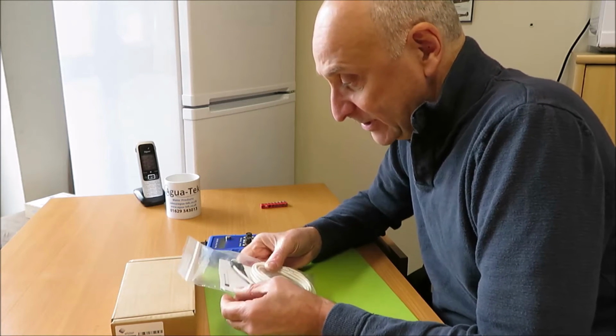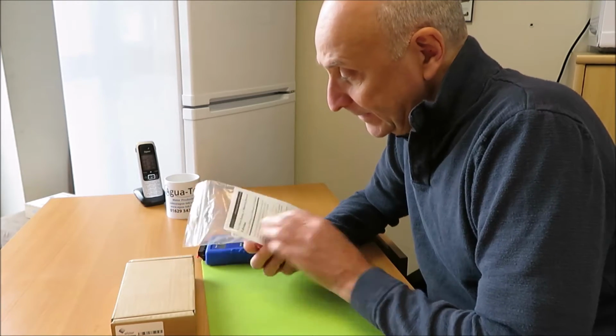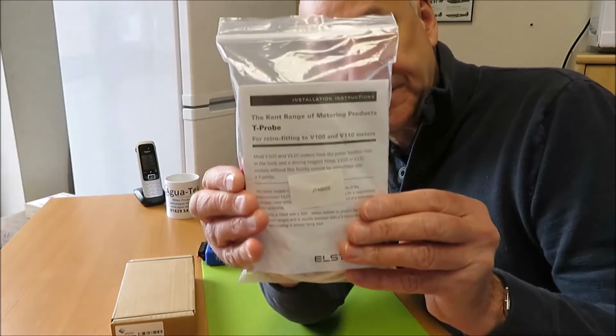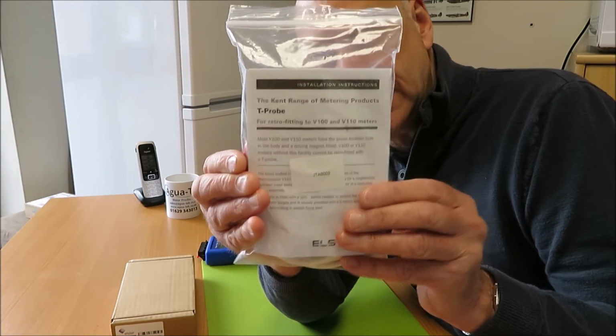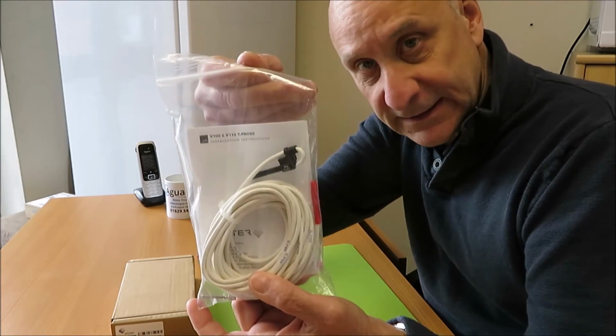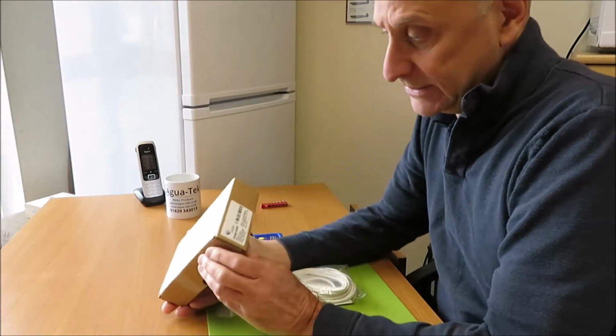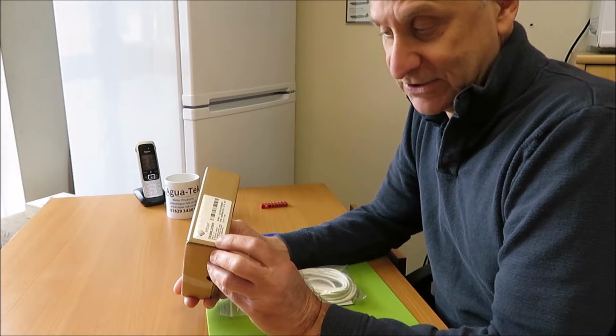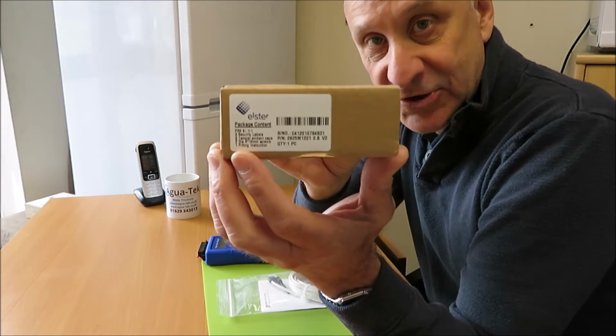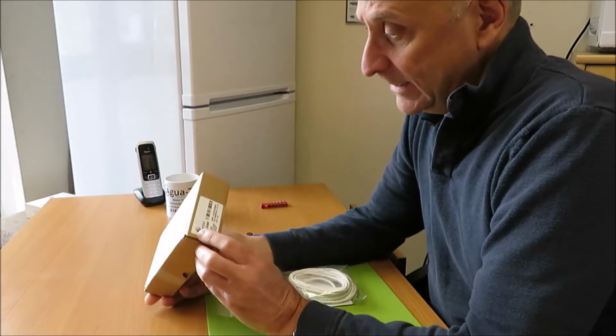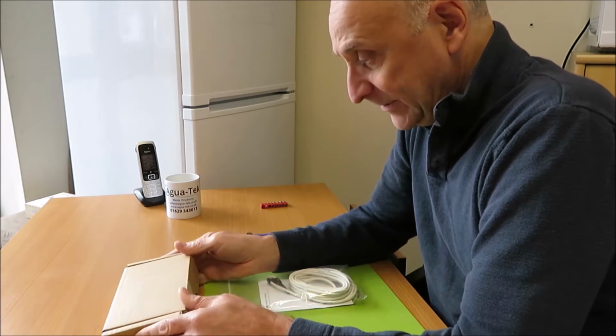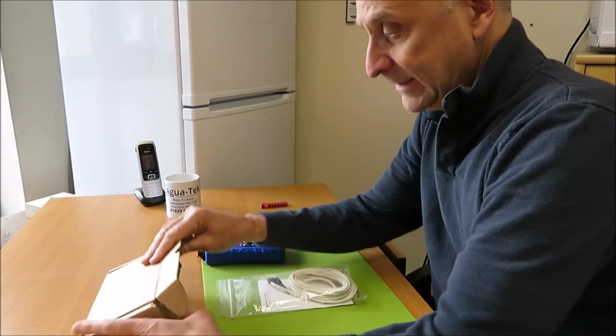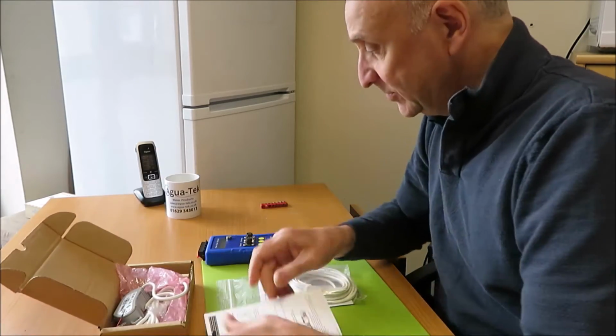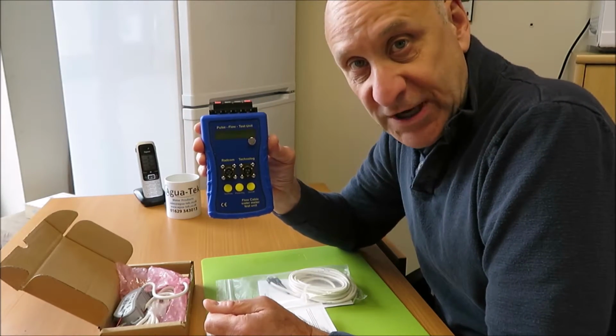The two units that I'm going to demonstrate today are the commonly known T-Probe, V100, V110 T-Probe, which looks like that, and the other sensor that I'm going to demonstrate is the PR6, which is exactly the same really to the PR7, apart from the PR7 goes on a larger meter. That's the Elster PR6, and this will be terminated shortly for the customer. I thought I would demonstrate how both of these can be tested using the Agua-Tek pulse test unit.